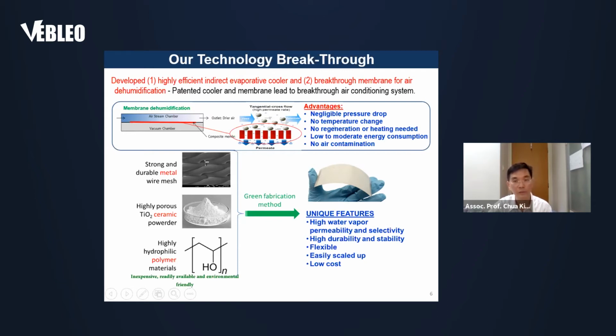So what is unique about this membrane? That there's negligible pressure drop. As the air goes through the membrane, there's little or no pressure drop. There's no temperature change, unlike some of the desiccants that you use to remove the moisture from the air, where as the moisture is being removed, it releases sensible heat to the air, so the temperature of the air goes up. But in membrane dehumidification technology, the temperature of the air does not change. So that is a very big plus point.